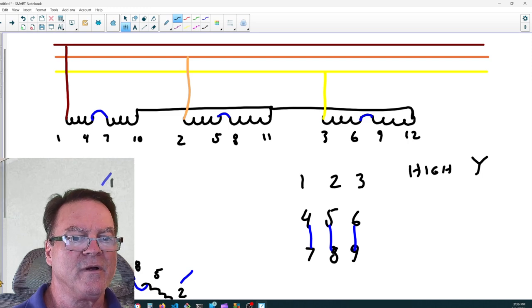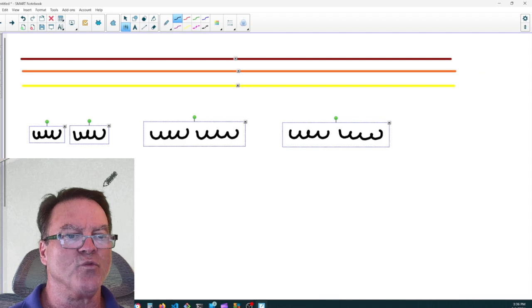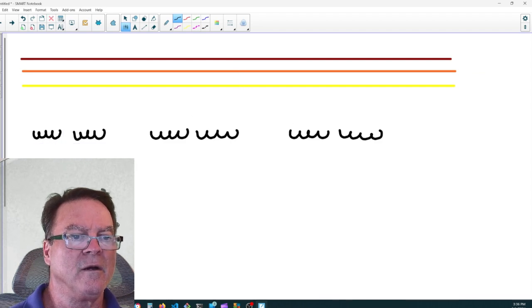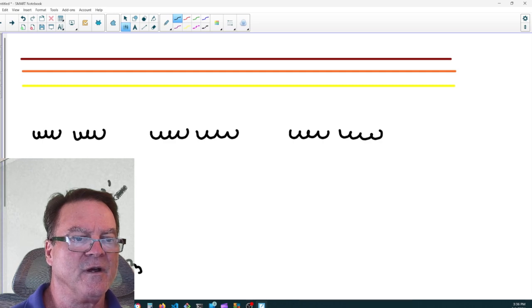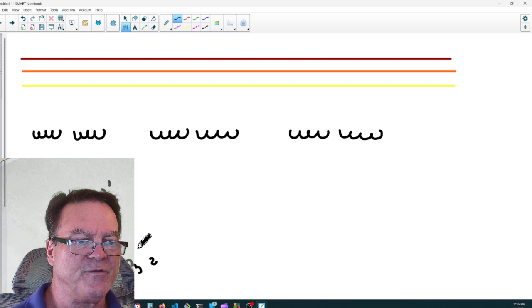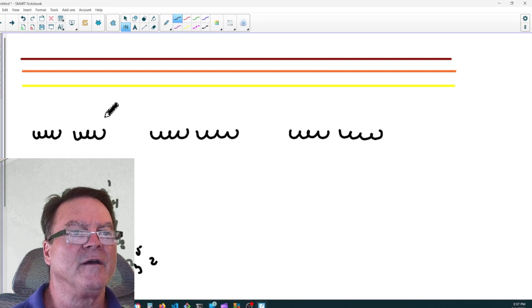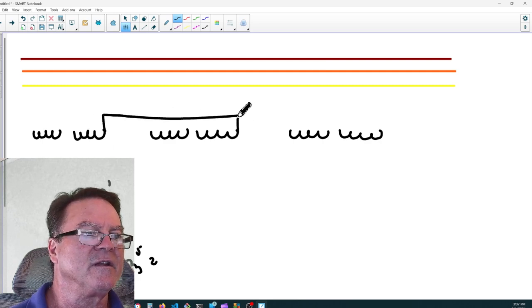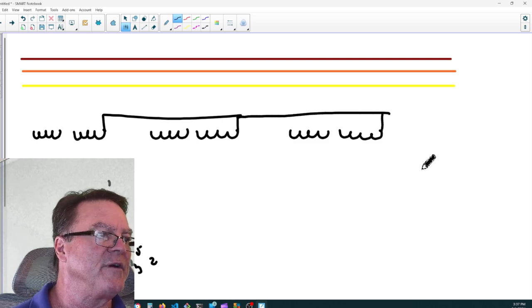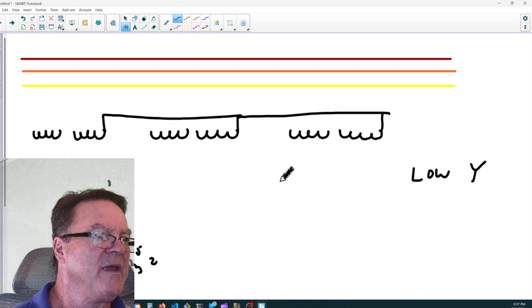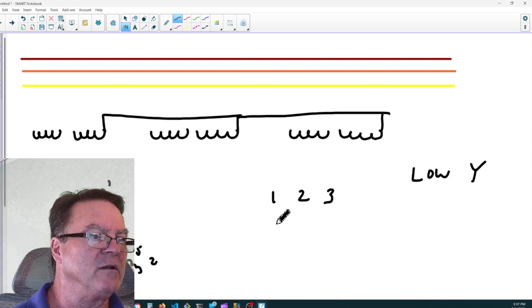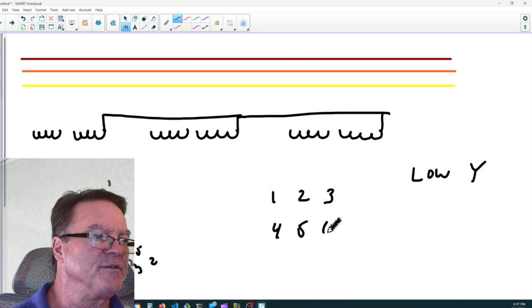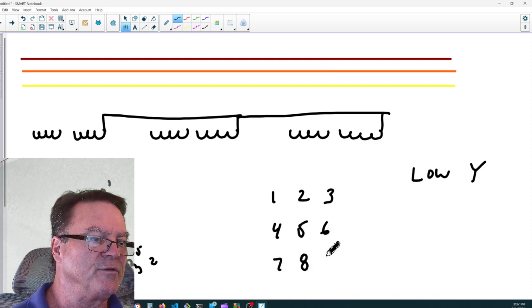And if I wanted to hook it up low voltage Y, I should have done a lot of this off screen, but 2, 5, 8, 3, 6, 9. Again, 10, 11, and 12 are already hooked together in the Y configuration. This is low voltage Y, and we're going to hook it up in parallel. You hook it up in series for high voltage, you hook it up in parallel for low voltage.